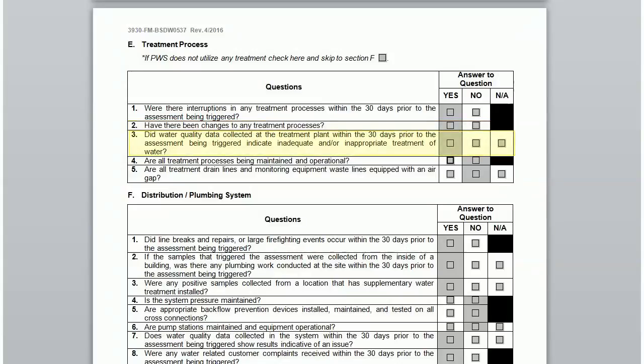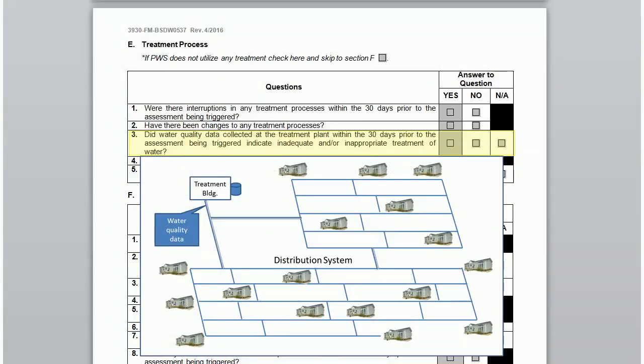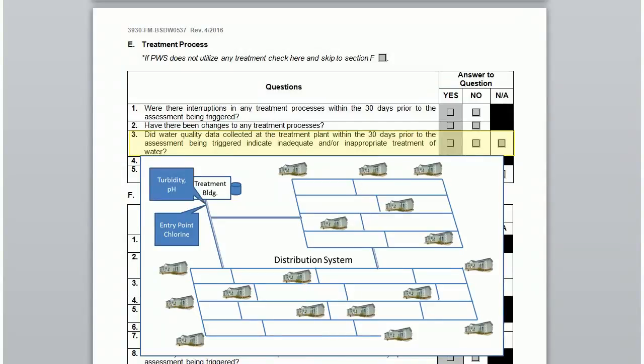The third question asks: does water quality data collected at the treatment plant within 30 days prior to the assessment being triggered indicate inadequate and/or inappropriate treatment of water? Community systems collect entry point chlorine residual data that would be used to answer this question. Some systems also collect turbidity and pH measurements at the entry point to the distribution.